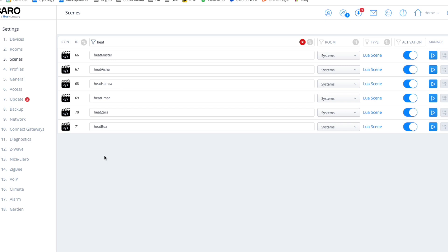As long as one room requires heat, the boiler will run. And therefore when room number two has the same issue—it's cold—valve opens and sends a signal. Then room one comes up to temperature and sends a signal. But because the other room—room two—still needs a bit of heat, it doesn't actually switch the boiler off. All it does is close the valves for room one. The valves remain open on room two and the boiler keeps running. And that way I can maximize the benefit of my heating and get the rooms up to temperature very quickly.